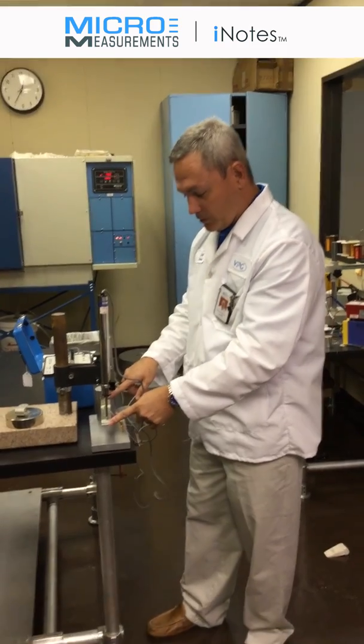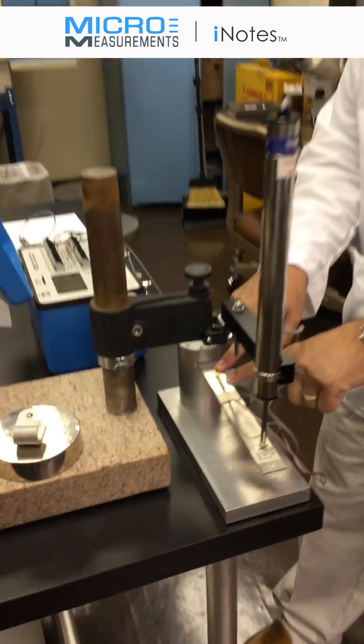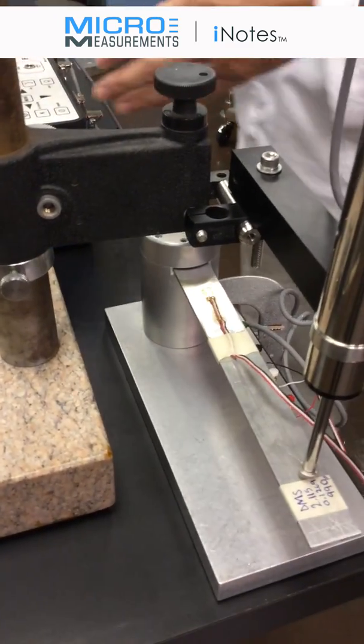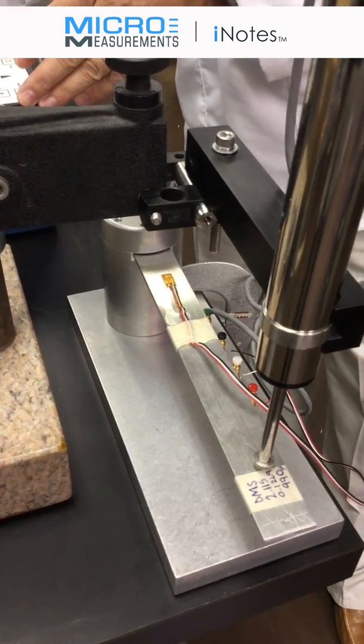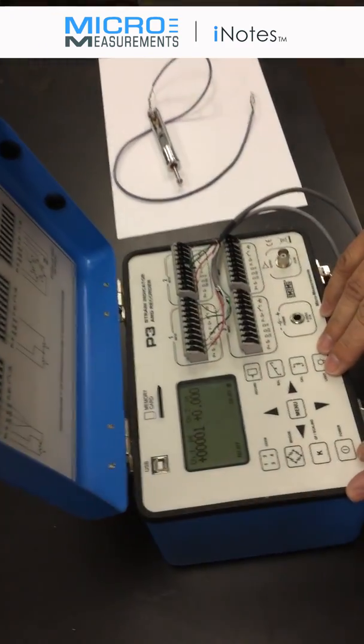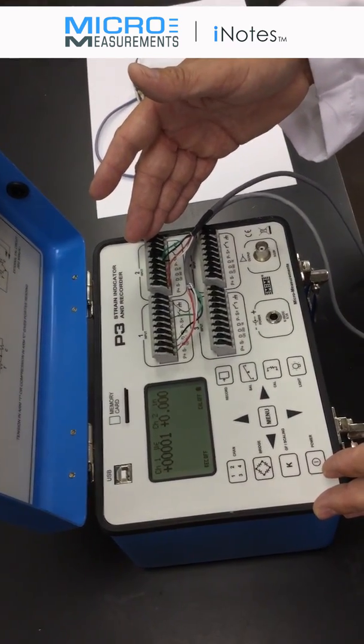I've also got one of our workshop beams that has one of our Micro-Measurements CEA series strain gauges mounted on it, and these two are connected into the model P3 strain indicator and recorder. I've got the strain gauge connected on channel 1 and the displacement HS100 connected on channel 2.